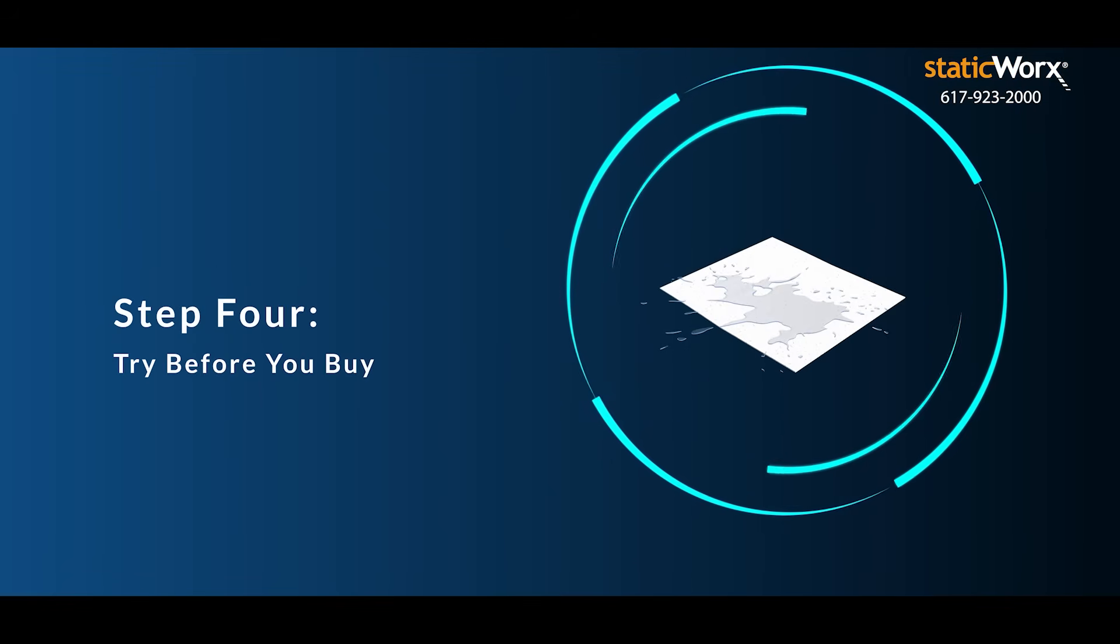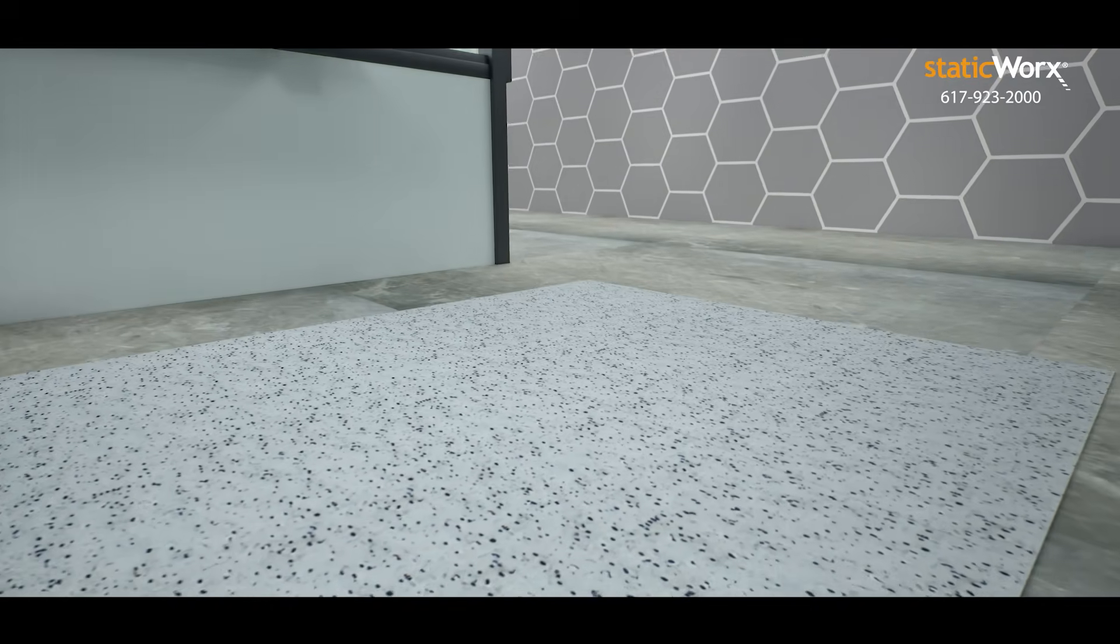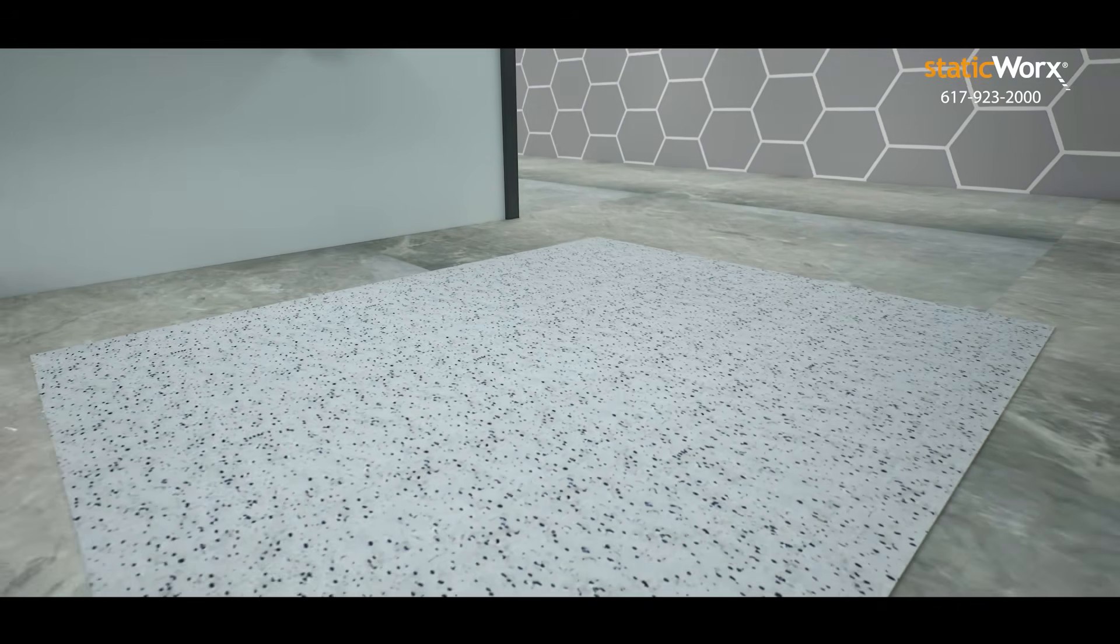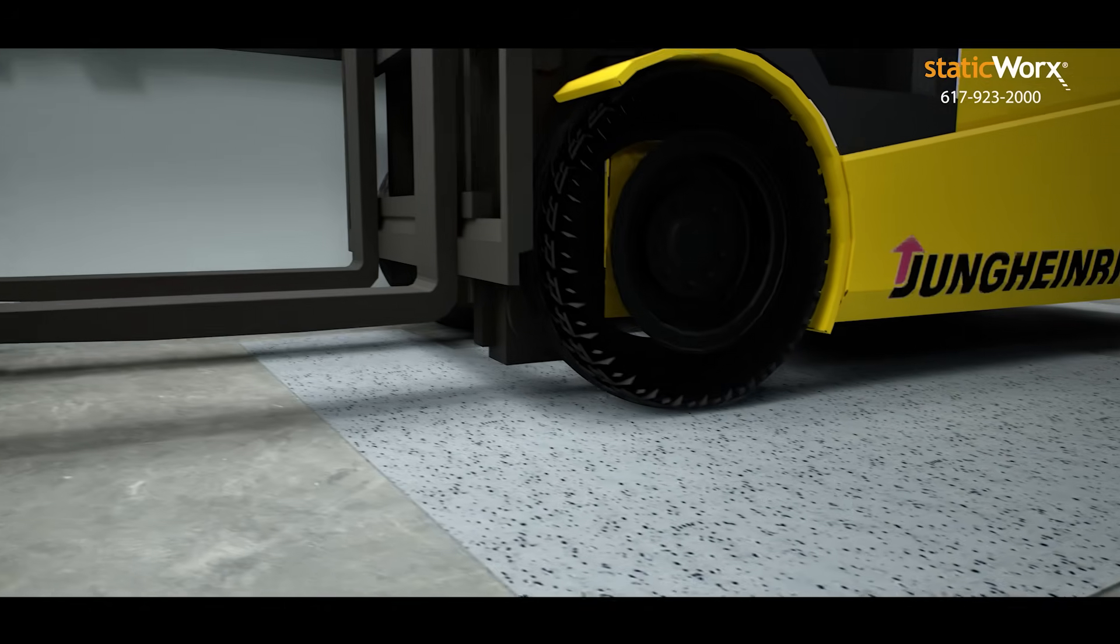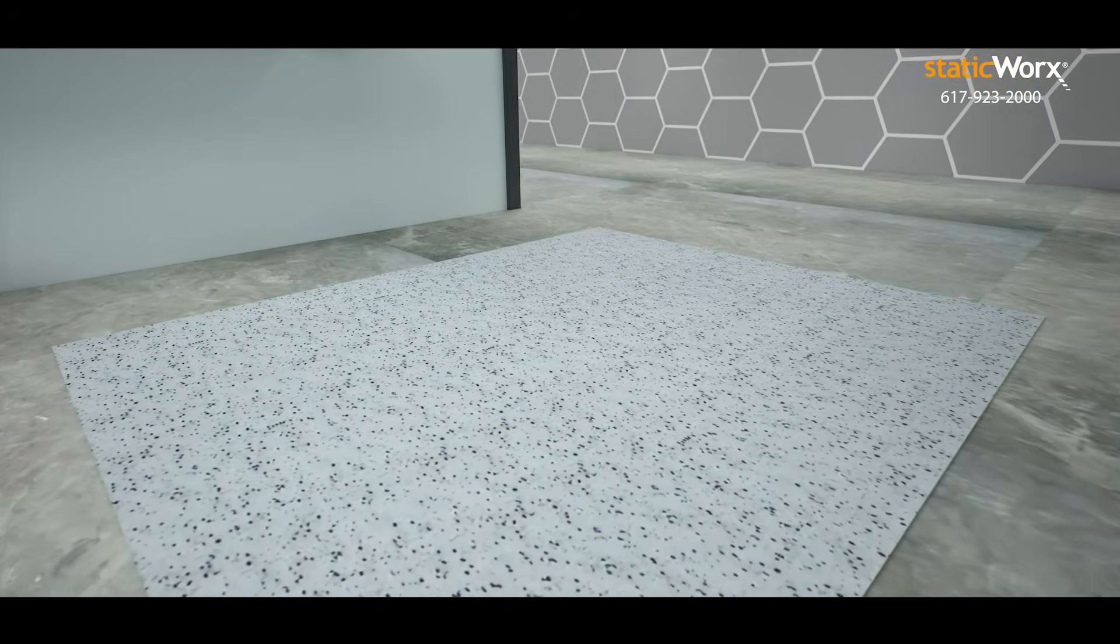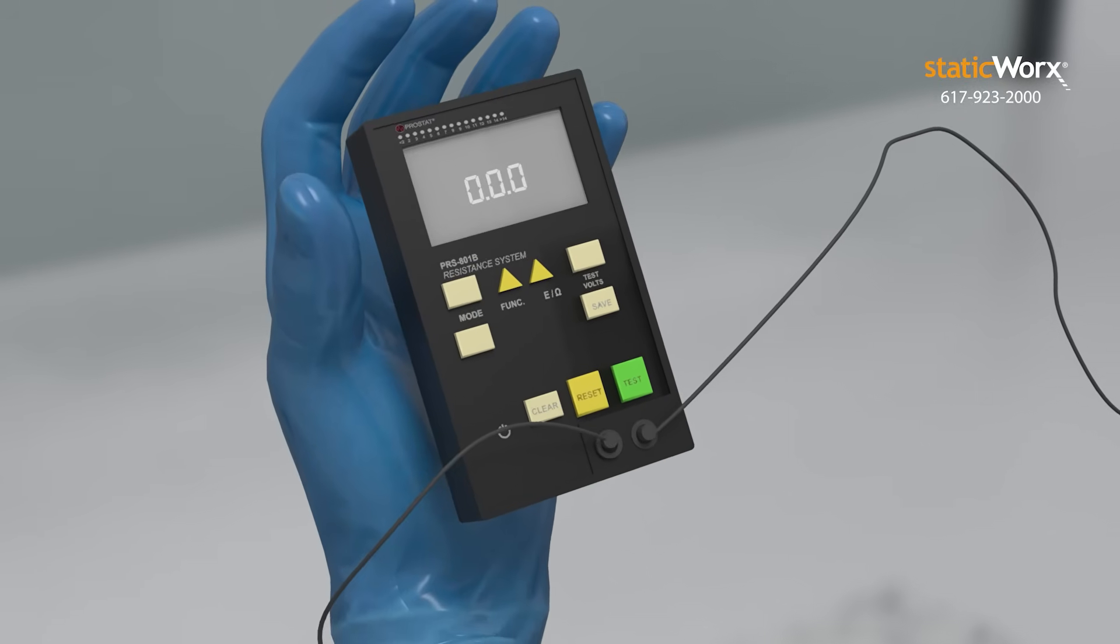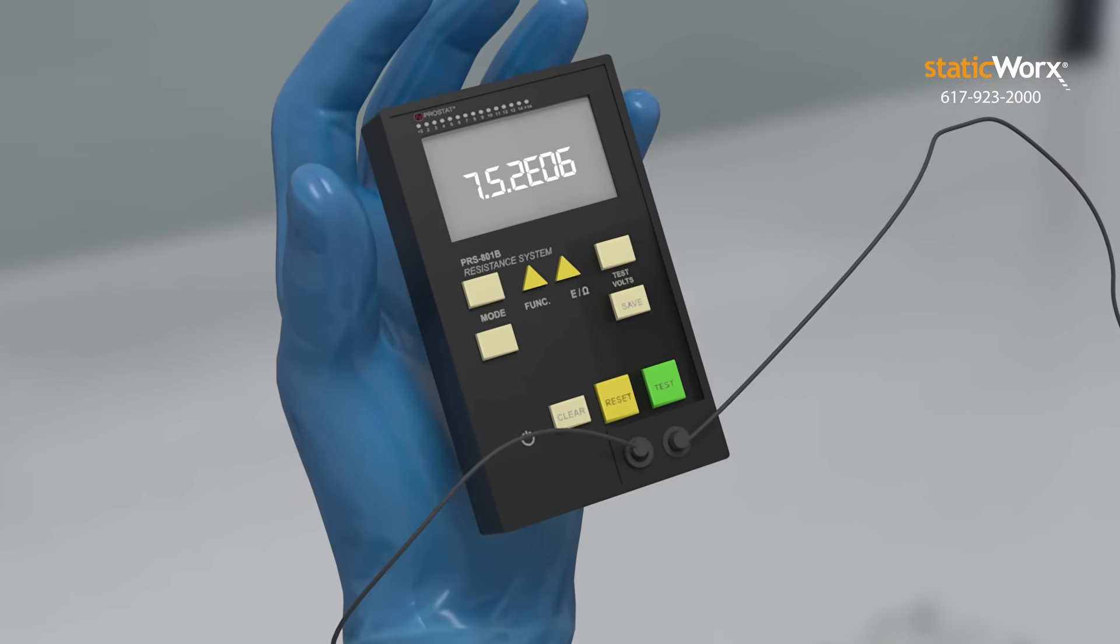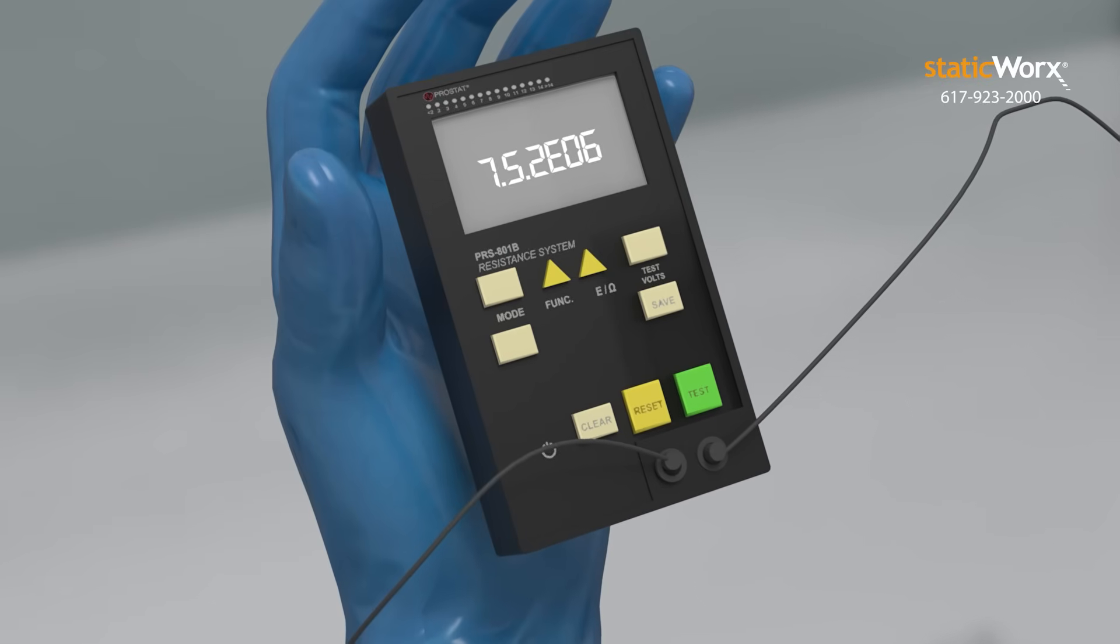Fourth, try before you buy. Before you commit, make the floor prove itself. Install a test patch, spill, stomp, scuff, drive over it. Let the floor take a beating for a month or two. See what it looks like, how it's held up, then retest for ESD compliance. If it passes inspection, you've found your floor.